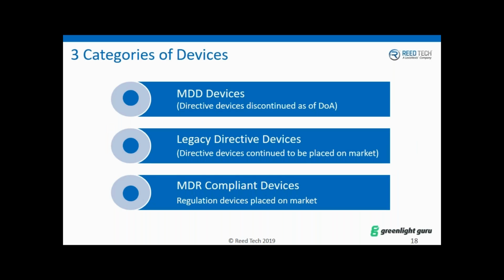To start our discussion, we need to look at three different groups of your product portfolio. You might have some products that are currently certified, and you're currently placing them on the market under the directive, in this example a medical device directive, but for whatever reason, as of the date of application, May 26, 2020, you elect not to continue with those devices, and you're basically pulling them off the market. The good news is that there are very few implications for those devices going forward after the date of application. None of the requirements for UDI would apply, but in the event those devices, which are now out in the field and being used by customers, are involved in a serious incident, you would need to report that into the new EUDAMED.